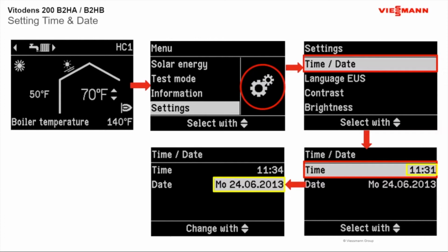But more importantly, our fault codes come with the time and date on them as well. So for troubleshooting, it helps a lot. Just for an example, I always tell this one because it happened, and we were able to find it through the time and date on the fault. It was a new installation, and the person hired a different company to install a generator. The generator was installed without updating or increasing the gas piping. The installer programmed it to come on and cycle every Wednesday to test itself. We looked at the fault code and saw that the fault was coming in every Wednesday at 7 a.m., when that generator cycled itself. It was actually sucking the gas out of the boiler. So that's why, to me, time and date is important. You can sometimes troubleshoot with that.